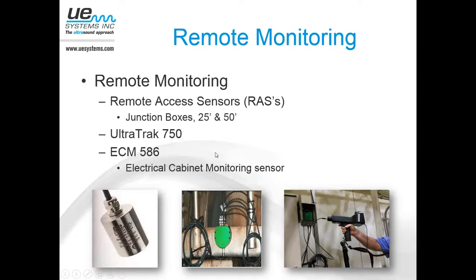We've got some permanent sensing applications we can address with UltraTrak 750, and we've even got some cabinet monitoring sensors that permanently stay inside enclosed switchgear and identify when there's some tracking or arcing conditions. So there's plenty of remote options in this changing world we live in, with more emphasis on safety and more emphasis on guards and shields. There's always a workaround and the ability to go out and monitor safely.